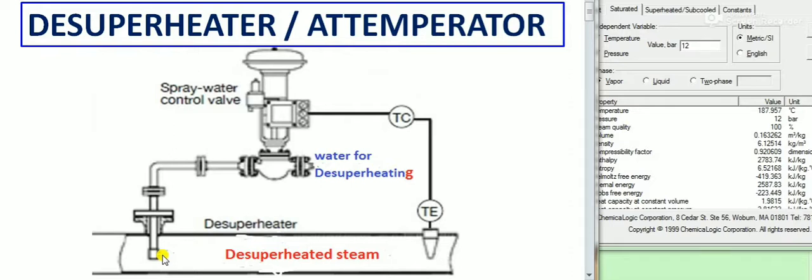It will get vaporized and reduce the steam temperature. It will not cause any harm. So we want to atomize the water being added to the de-superheater for this purpose. That is the spray nozzle arrangement. That is the main purpose: you want to make droplets, so we have spray nozzles, venturis, or atomizers.